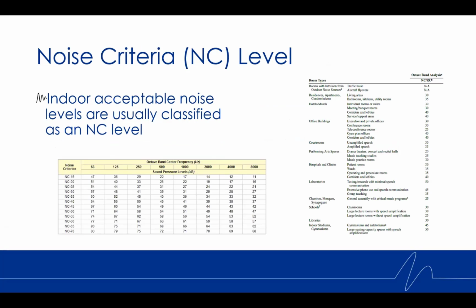Now, there's a way to categorize these and specify levels. So for indoor noise, we typically use something called an NC, or a noise criteria level. Now, if you look at the chart on the right, that's a chart issued by ASHRAE in the ASHRAE handbook. And these are some general guidelines you can use to determine what a typical NC level would be. So for example, a classroom would be NC 30. A corridor can be a little bit louder, so it can be NC 40.